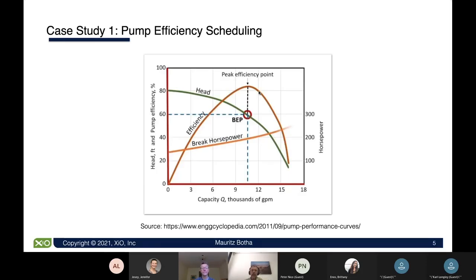We also see that as aquifers get overdrawn and depleted as the season goes by, you may shift on this curve towards a much less efficient point. And as the rainfall season comes and the aquifers fill up, you shift to the other side. One other thing we regularly see is that people over-design these pumps by about 10 to 20% to account for changes in system performance over the years. The net result is you hardly ever work at this peak efficiency point.